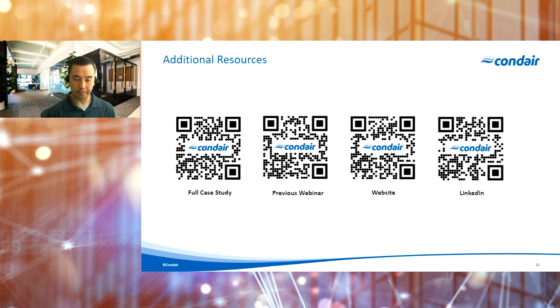So once we hit set point, if we have face dampers, we can close off the airflow to the pads themselves, and then we can open up the bypass dampers and modulate or control to a mixed air condition from there. The other way that we've seen it done is a bit more inefficient, but is effectively dew point control. So you over humidify, overcool as much as you can, and then you use heating coils and cooling coils downstream to trim to your desired set point afterwards. That's certainly going to be a lot less efficient way of doing it, but it is a way of achieving tighter control while still being able to use an evaporative media type system.